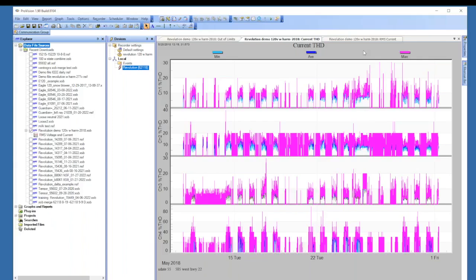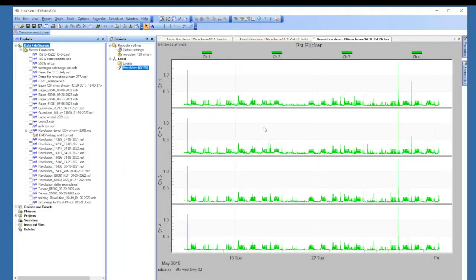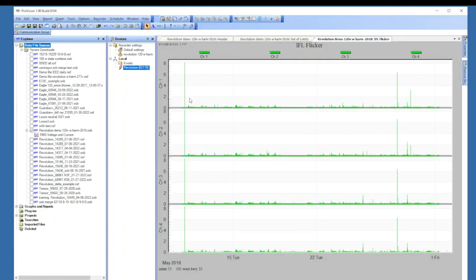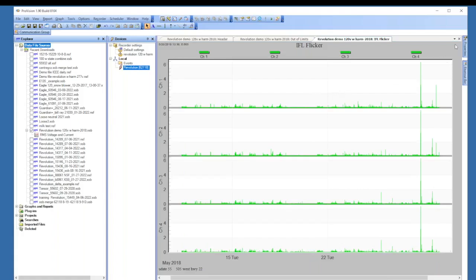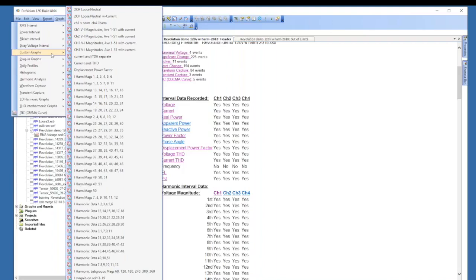But if it is too high, the whole problem with harmonics is heat. And that heat will go back and damage a transformer, overheat the transformer, and cause premature failure on the transformer, among other things. The PST was, so anytime you see the green like that, you'll know it's averages. So 1 is the stake in the ground. So basically, except for a few little spikes here, overall there really wasn't much in the way of flicker. And the IFL, you have to go through and compare IFL to voltage and current. Now I do have custom graphs out there that I can send you. The custom graphs, when you load them, you can find them underneath custom graphs.